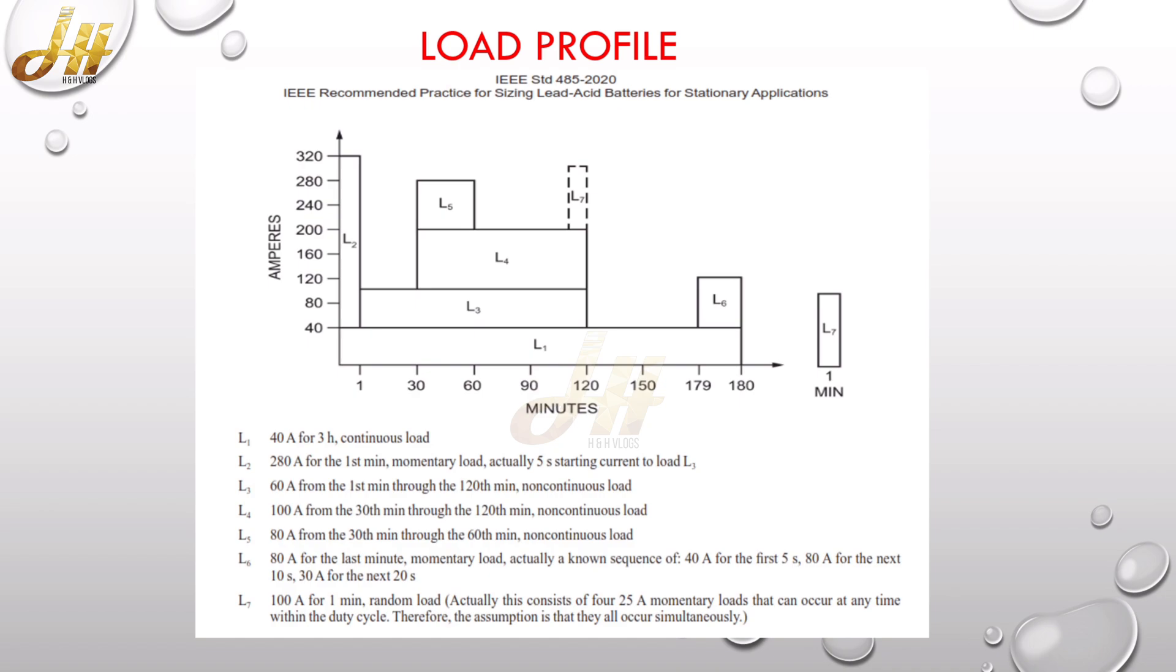Now you can see L1 is continuously for three hours, which is 40 ampere, and L2 is 280 ampere. So the instant load at minute one is 320, which is 280 plus 40 ampere. Likewise, the different loads are mentioned below: L2 is 280 ampere, L3 is 60 ampere, L4 is 100 ampere, and L5 is 80 ampere.